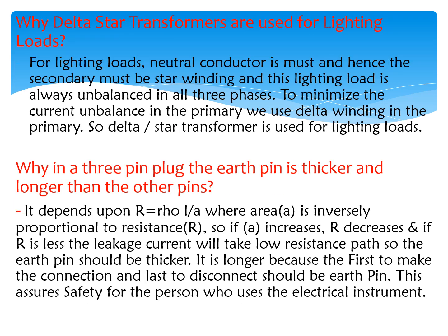Why are delta star transformers used for lighting loads? For lighting loads, a neutral conductor is a must since all lighting loads are single phase loads, and hence the secondary must be star winding, and this lighting load is also typically unbalanced in all the three phases. To minimize the current imbalance in the primary, we use delta winding in the primary.